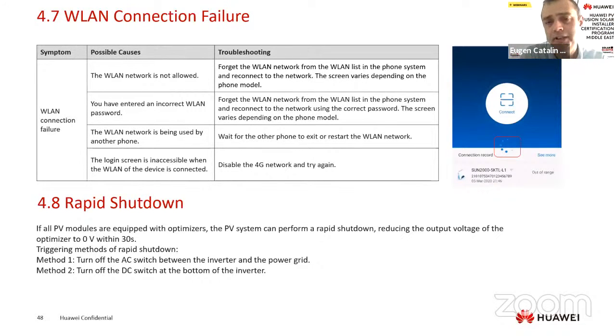and after that the Wi-Fi was generated. Second, that we meet especially on iOS, is there an option on the Wi-Fi? It's a private network. If you disable that option, you cannot connect, because this is a private network for the inverter. It's the inverter network locally. There is an option in the settings of the inverter Wi-Fi that if you disable it, you cannot connect to the inverter. This fault is not a fault. The customers are not paying attention and disable that anyway.